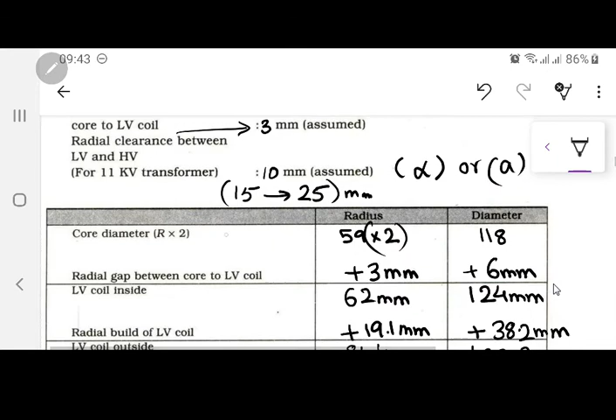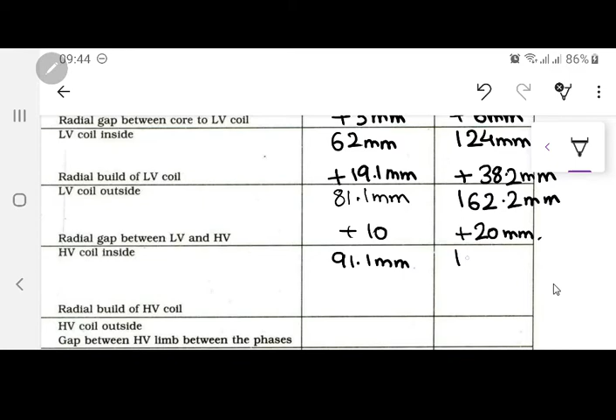Okay, the radial gap between the low voltage and high voltage is kept as 10 mm. So I'm going to add over here plus 10 mm, and here the radial gap will be added as 20 mm, because this is the diameter column. So what will be the high voltage coil inside diameter? This will be 91.1 mm, and this one would be 182.2 mm.